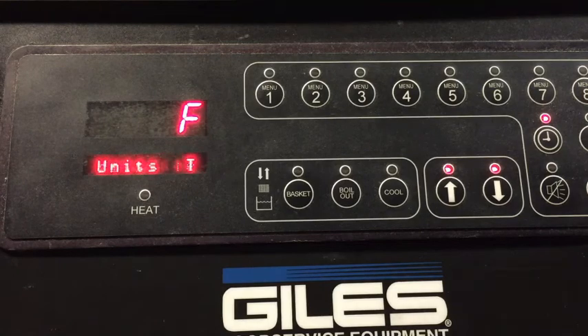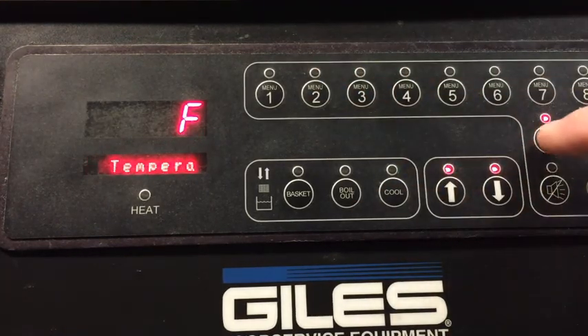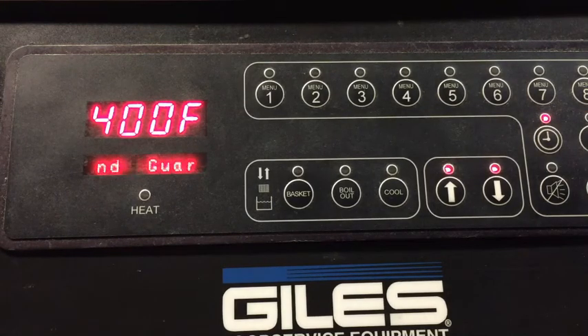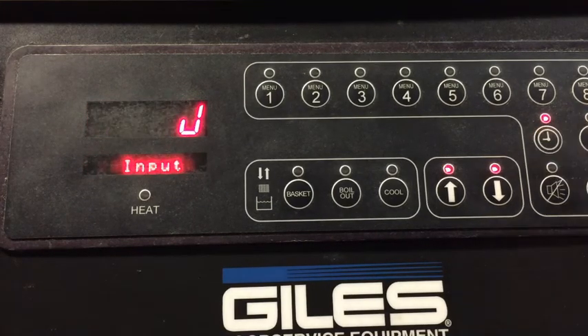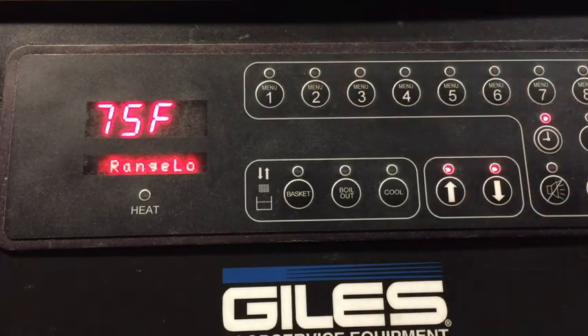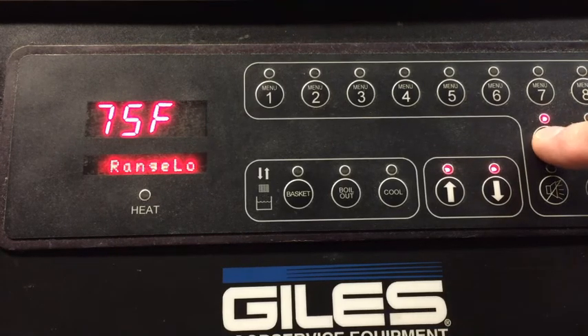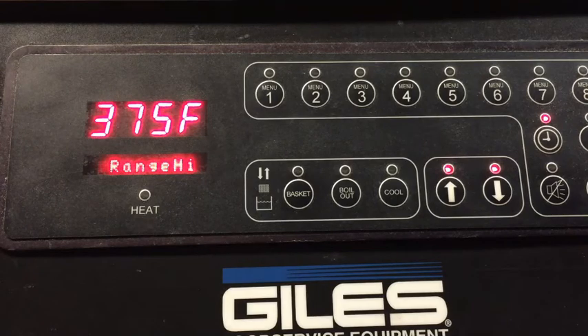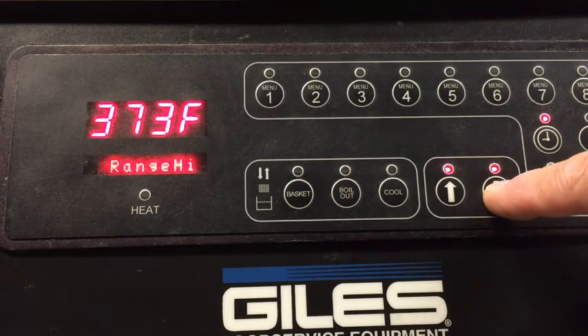Okay, and here we're going to read everything, the temperature units Fahrenheit. We can go ahead and change that to Celsius if that's what we wanted, but we'll stay in Fahrenheit. Hit the clock to get advanced to the next. Guard band will always be at 400. It's a function that we don't use, so we just leave it set up there at 400 and it stays out of our way. Input J-type thermocouples. That's what it's looking for. Range low, they can never set a temperature less than that range low, which is 75 degrees. Range high, 375. Normally we'll go ahead and bump that down to 350.